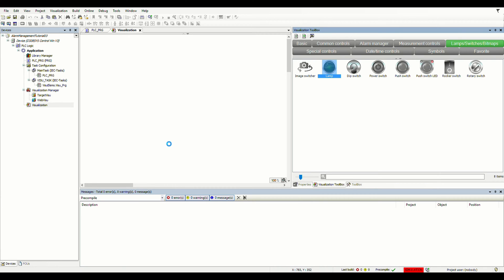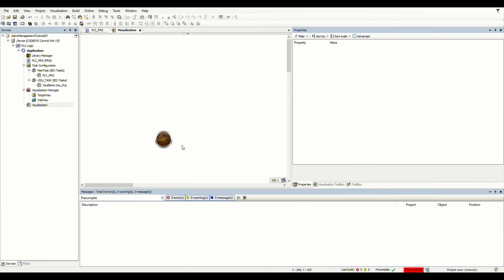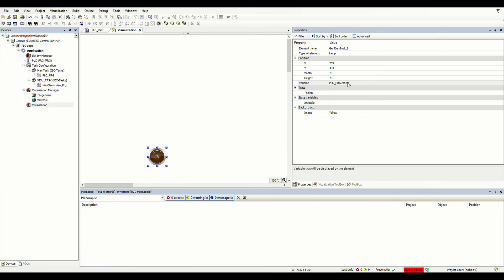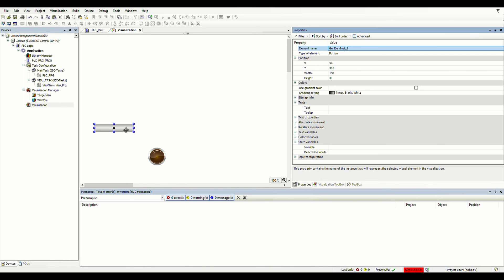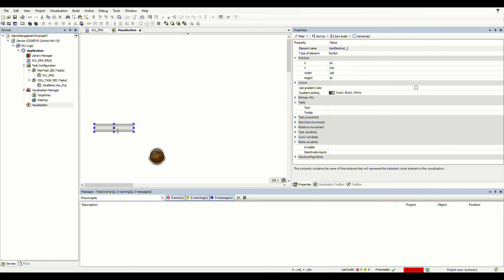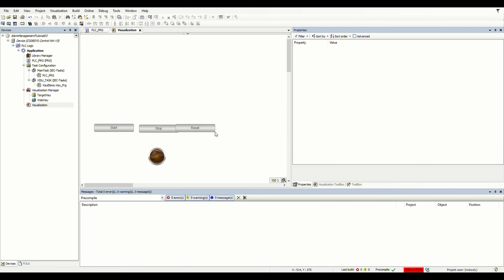I've also created the visualization. We have a pilot lamp to show the state of the motor using the motor variable — PLC_PRG.Motor — as the variable for this pilot lamp. I'm also going to use a couple of buttons to start the motor, stop the motor, and reset the counter. So we have a start button, a stop button, and a counter reset push button, and I need to associate them with the proper variables in the PLC program.